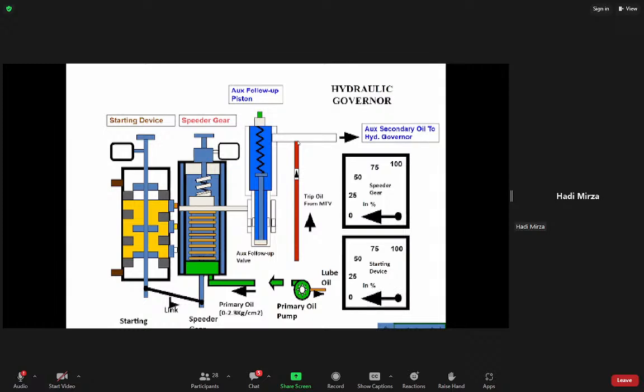There's some graphic issue, I think so. Basically, that is what I have said earlier. The starting device will act as a fulcrum here, and it works against the spring, and then in turn opens the port sleeve here in the follow piston. Basically, what happens here is trip oil pressure will be draining continuously until the port is closed here. This is the sleeve of the follow piston, which closes the draining of the trip oil.